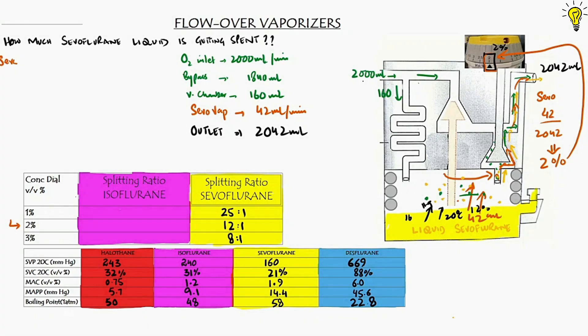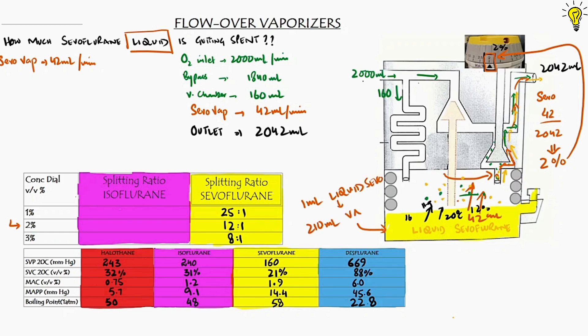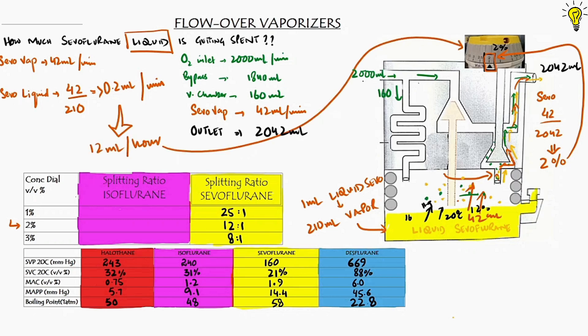Now, 42 ml/min is the sevoflurane vapor. But how much liquid sevoflurane is being consumed? One ml of inhalational liquid generates 210 ml of vapor. So 42 ml vapor ÷ 210 = 0.2 ml liquid per minute, or 12 ml of liquid sevoflurane consumed per hour at a 2% concentration dial and 2 L/min fresh gas flow.